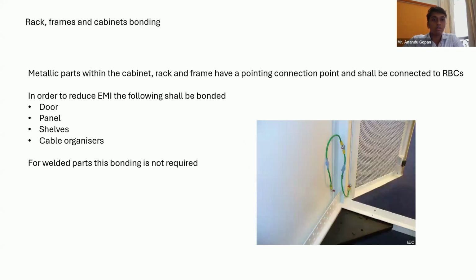For EMI/EMC concerns, it is better to connect the cabinet doors, panels, and cable organizers to a common place, such as the equipment body itself, or to the RBC. In the previous slide, you saw this RBC, right? Rack bonding conductor, or rack bonding bus bar.